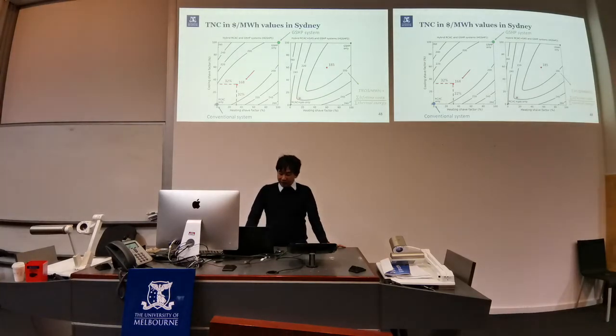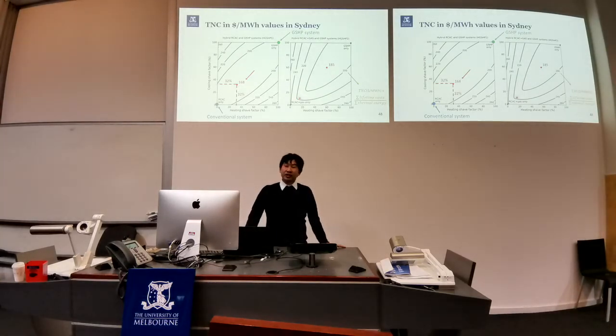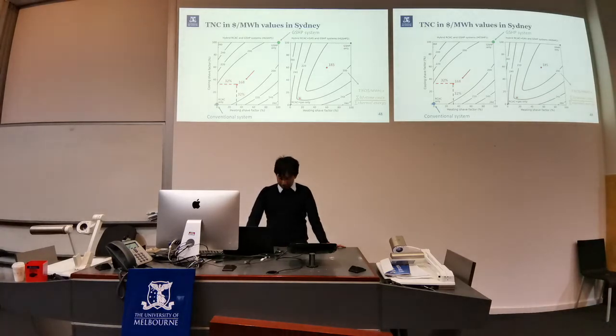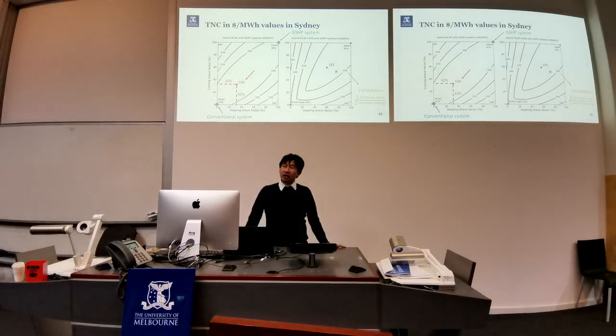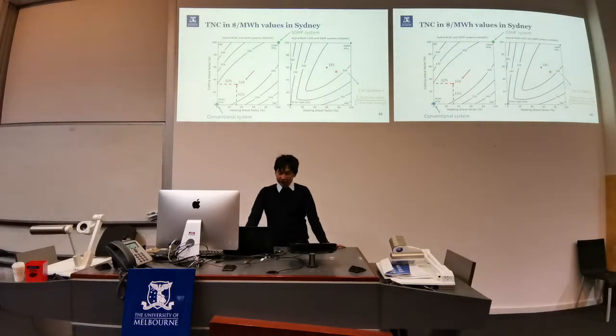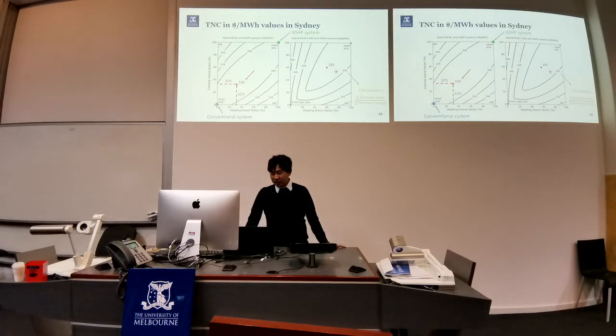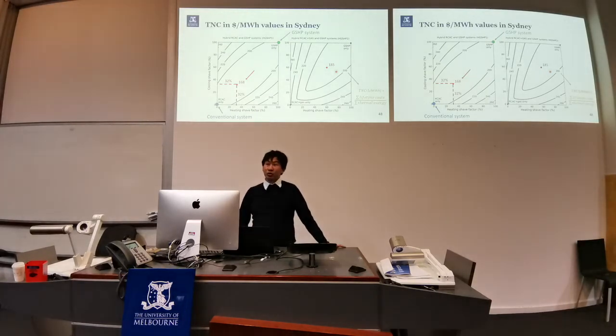For this hybrid system, the ground source heat pump needs to be designed to provide about 32% of peak heating and cooling load. Similarly, for the second hybrid system, the lowest normalized cost is $185 per megawatt hour. For this system, the ground source heat pump needs to provide about 60% of peak heating and cooling load.